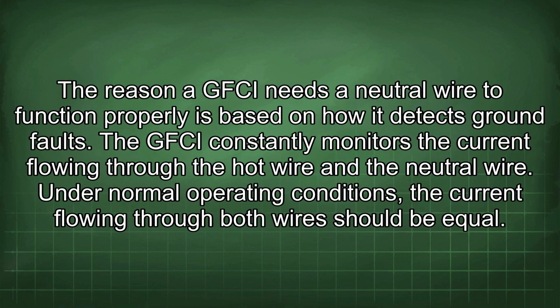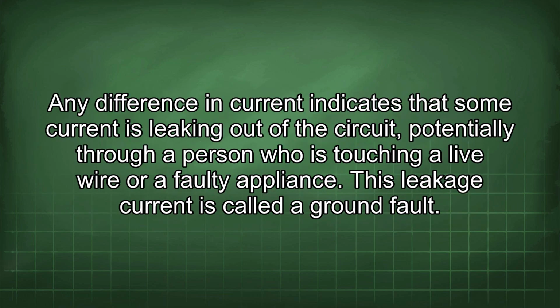The reason a GFCI needs a neutral wire to function properly is based on how it detects ground faults. The GFCI constantly monitors the current flowing through the hot wire and the neutral wire. Under normal operating conditions, the current flowing through both wires should be equal. Any difference in current indicates that some current is leaking out of the circuit, potentially through a person who is touching a live wire or a faulty appliance.